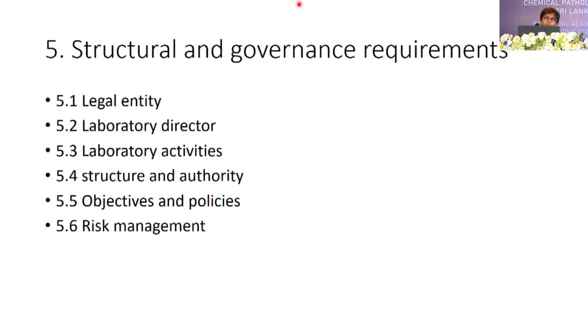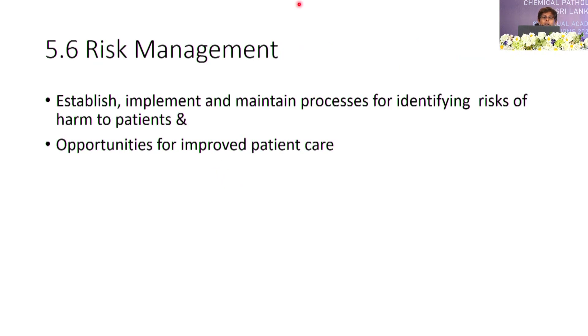In clause 5.6, risk management comes in. If you read this standard carefully, the word 'risk' appears in about 100 places. The key highlight is to establish, implement, and maintain processes for identifying risks of harm to patients, and also to look actively and proactively for opportunities for improved patient care.